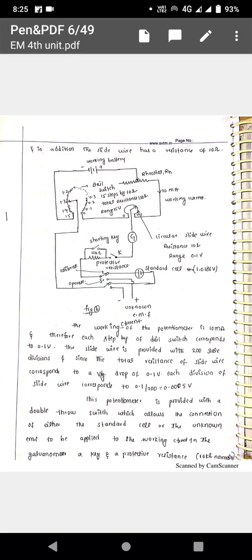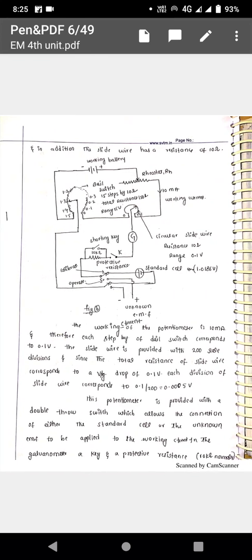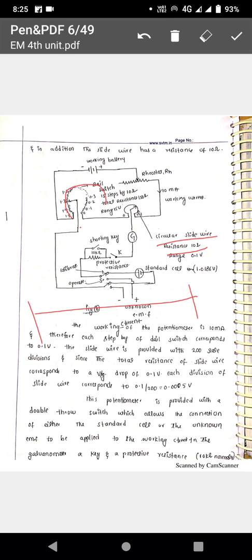In Crompton's potentiometer you can see a dial switch with 15 steps and a circular slide wire. Because the 200 cm slide wire would be very awkward, a circular slide wire is provided for Crompton's potentiometer. The same principle as the basic slide wire potentiometer is applied. Unknown EMF and standard cell are required — the standard cell is needed for standardization. The circular slide wire has a resistance of 10 ohms and a range of 0.1 volts, making standardization and measurement easy.